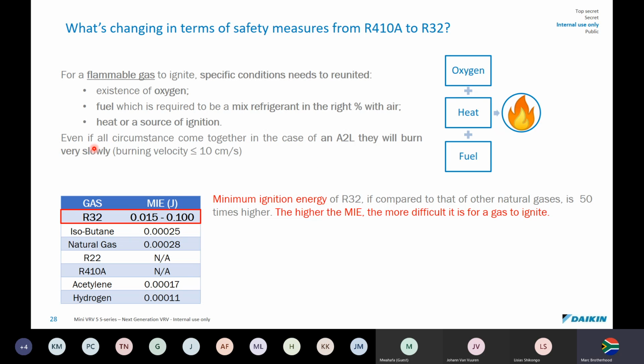So if you look at this rating, A2L refrigerant, which is what R32 is. They say if all circumstances come together, say you've got oxygen, you've got a flame to light it, and the fuel will be the R32, you will see it'll burn very, very slowly. The burning velocity is less than 10 centimeters a second. I mean, propane, butane, acetylene, that's crazy speeds that they burn at. This travels and burns very, very slowly.